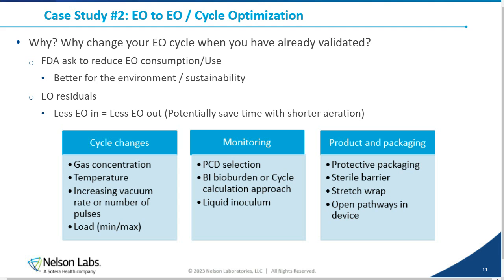Well, the first answer to that is the FDA's asked us to. The FDA's asked to reduce EO consumption and use. This is better for the environment and it's more sustainable. The other is EO residuals. So the basic formula is less EO in means less EO out. Where that's really going to potentially save some time is going to be your aeration. If I'm not putting as much in, or if I'm doing different cycles and using vacuum more to get it out or to get it in the first place, then potentially I can save on some aeration. Again, less EO in, less EO out, so I can save some there.